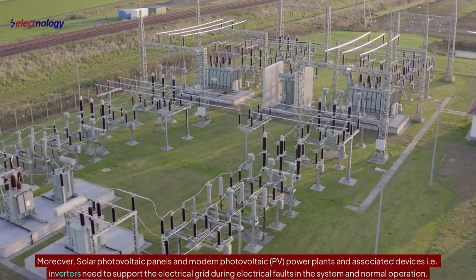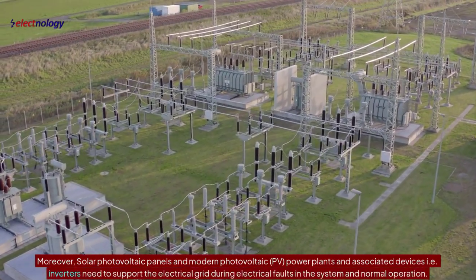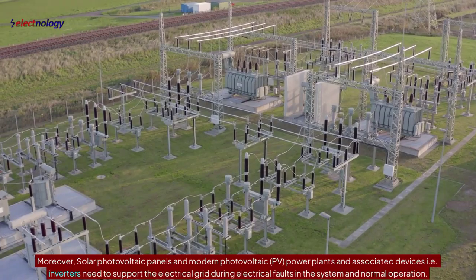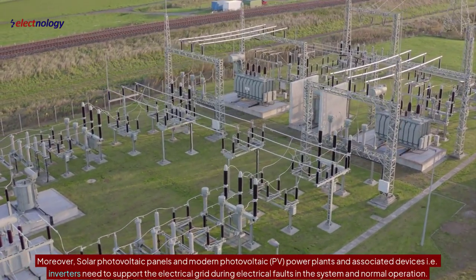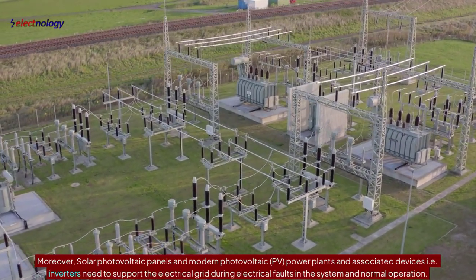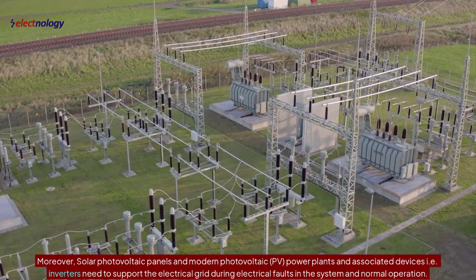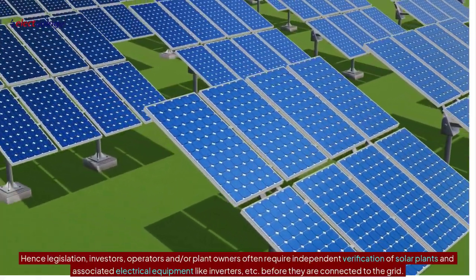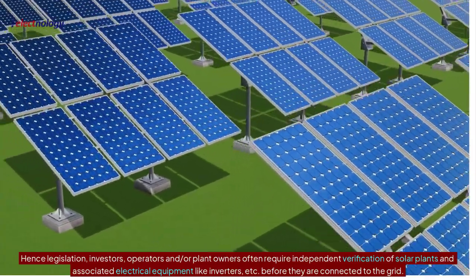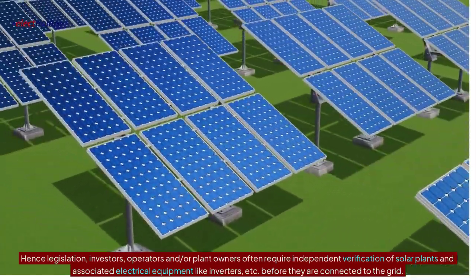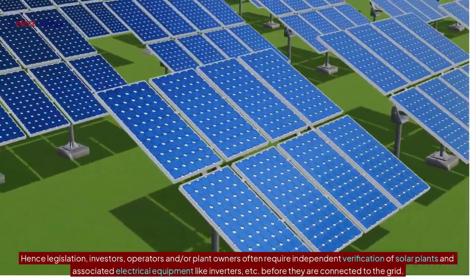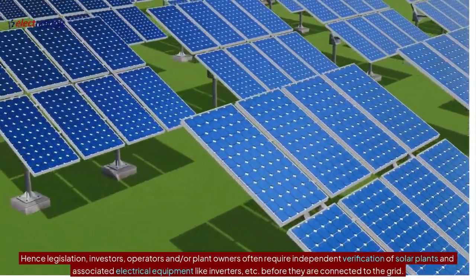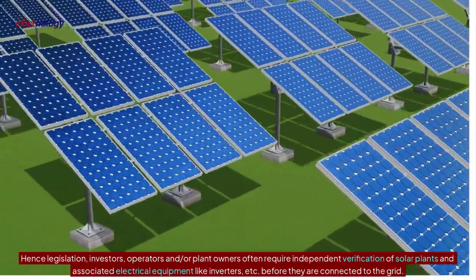Moreover, solar photovoltaic panels and modern photovoltaic (PV) power plants and associated devices, i.e. inverters, need to support the electrical grid during electrical faults in the system and normal operation. Hence legislation, investors, operators and/or plant owners often require independent verification of solar plants and associated electrical equipment like inverters, etc. before they are connected to the grid.